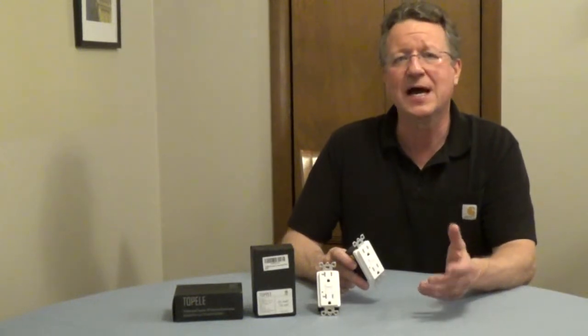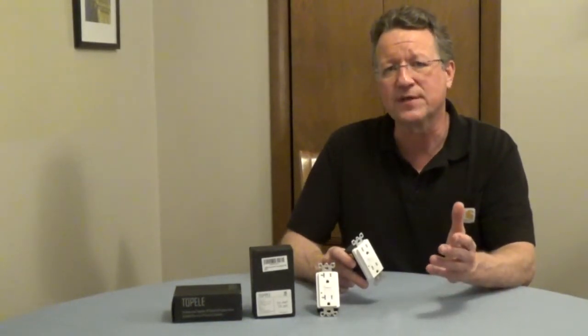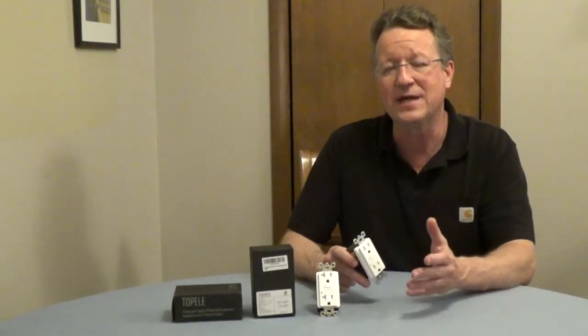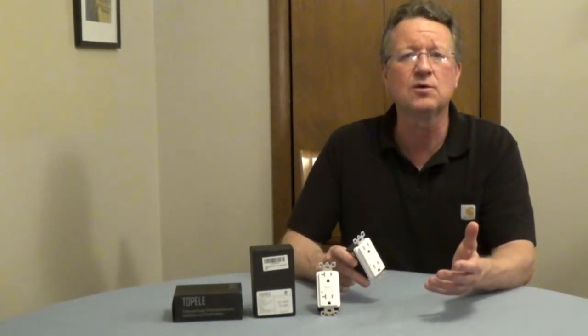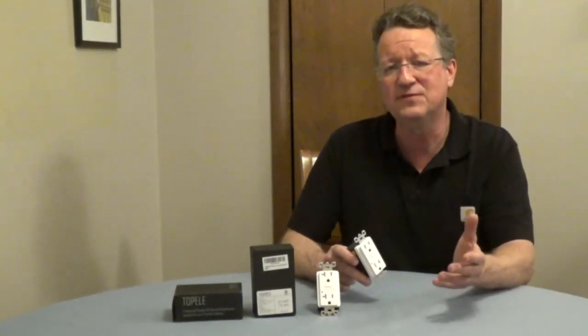When you're replacing an outlet with a GFCI, the first thing you need to know is whether that circuit is 15 or 20 amp. So take a look at the breaker or the fuse. It's going to be marked 15 or 20.